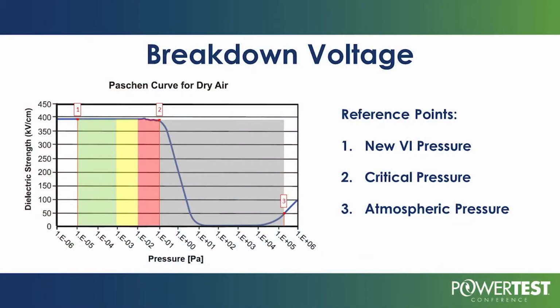because if your maintenance cycle is 5 years, you might get to failure before your next maintenance cycle. So you could have a piece of equipment in service that would not interrupt a fault, a severe fault, or would not do what it's supposed to do and protect your people and your equipment like it's supposed to operate. So it's real important you understand this. It's basically manufactured in the 10^-5 Pa range or lower.